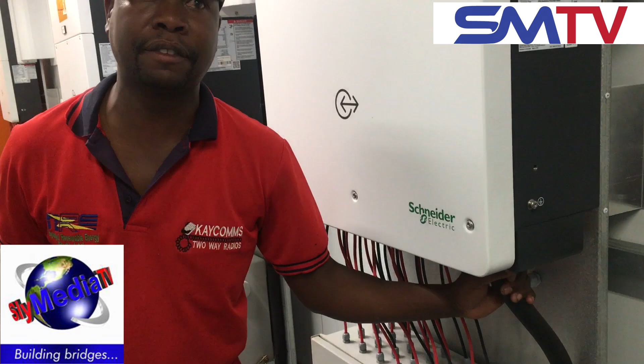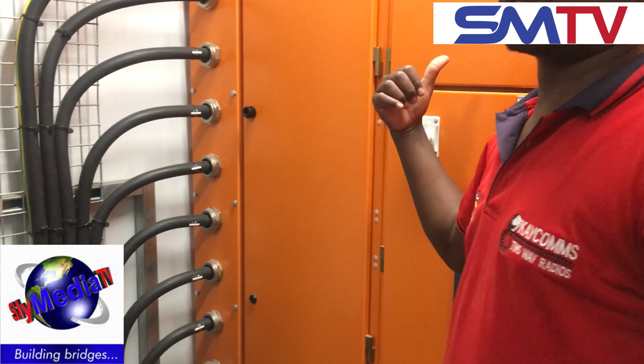So all the cables and the inverters are now coupled inside this guy. This is now our AC combiner board, which combines 20 inverters on this side. Then the outside inverters, the cables come also from outside to here, and they are coupled inside here again. Then from there, all the inverters are coupled on one bus bar, which is 3-phase.